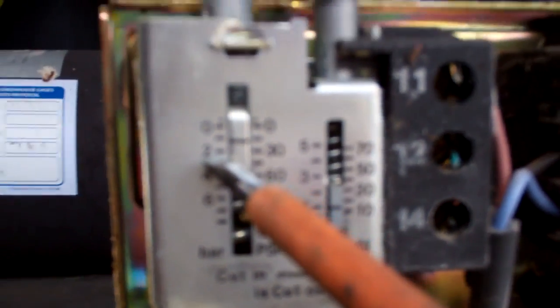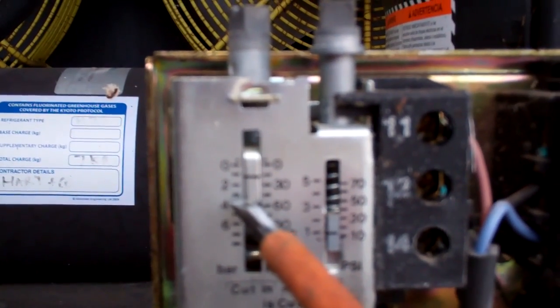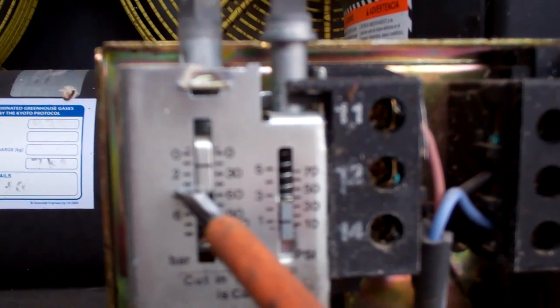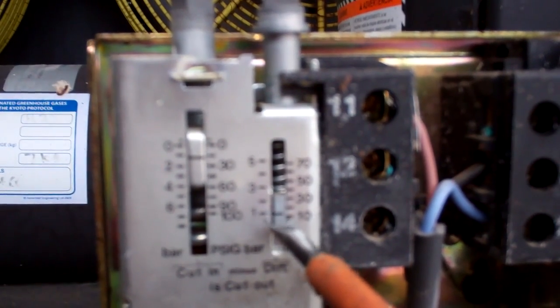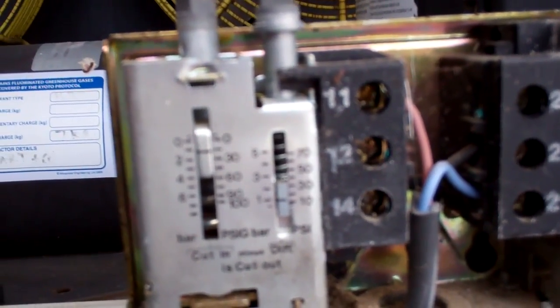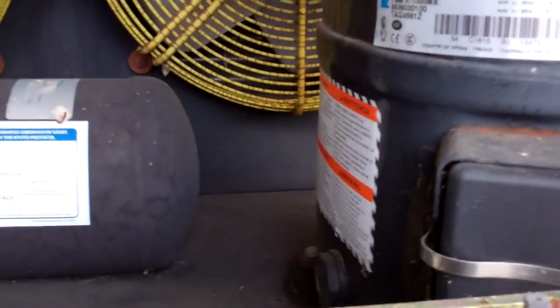I would say the diff is set too close on this. This should be really sort of, it's on one bar, 15 psi. Then you'd probably run it at 40, something, 40 psi. Maybe, you know, maybe 30 on the diff. So it's cutting out about 10. Because the high temp, it's going to run around sort of minus five, evaporator at the lowest temperature really. So there's plenty. Don't need to nearly pump it down into a vacuum.